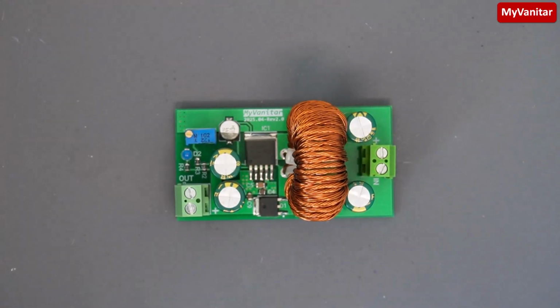It is true the controller is rated at 5 amps, but that 5 is the switching current maximum at 25 degrees C. This doesn't mean the output current.